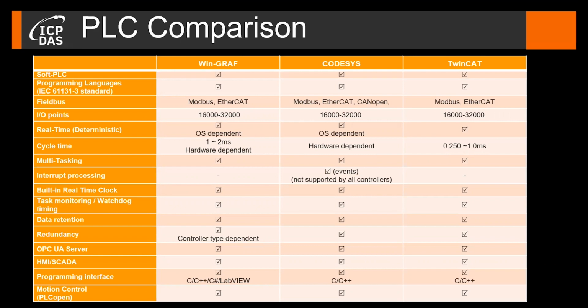The advantage of a soft PLC like Win-GRAF over a traditional PLC is that soft PLCs are more flexible for extension. For Industry 4.0, flexibility is a key component. So soft PLCs, such as Win-GRAF, are developed with Industry 4.0 in mind and can be flexibly expanded to support M2M and IoT functionality. In addition, because the runtime runs on the PC, it does not just run the PLC logic, but also various applications in parallel. For example, web server, HMI, and OPC server all run in parallel with the PLC application on the same Windows PC or Linux PC platform. In addition, soft PLCs use vendor-independent programming languages. They use the standardized IEC 61131 programming languages.